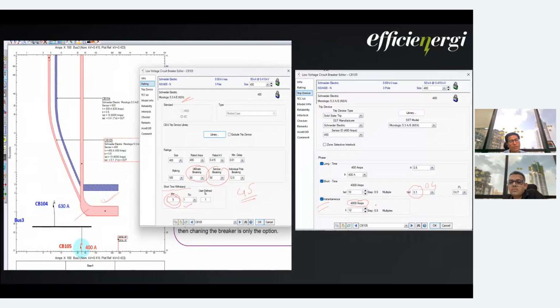So disablement of instantaneous in this particular case will break your breaker when there is a fault. You may achieve the selectivity, but on the network, if the fault occurs, this breaker is going to get damaged, and there will be no starting it again. So you will be losing the complete line of this breaker.